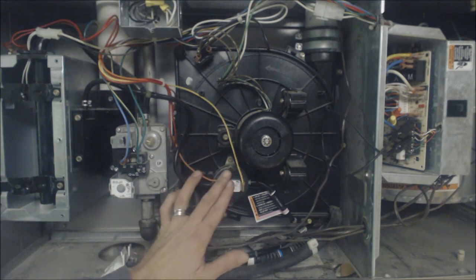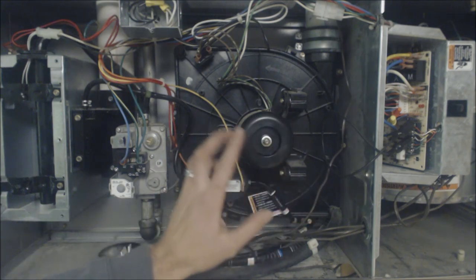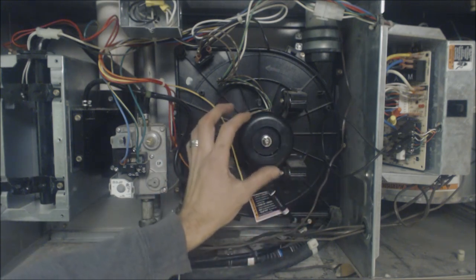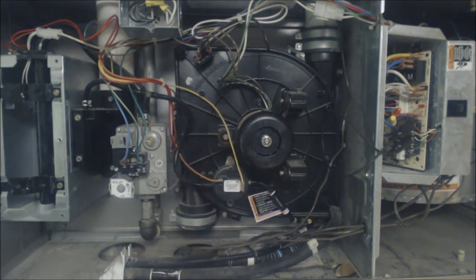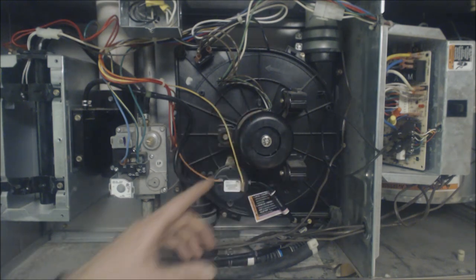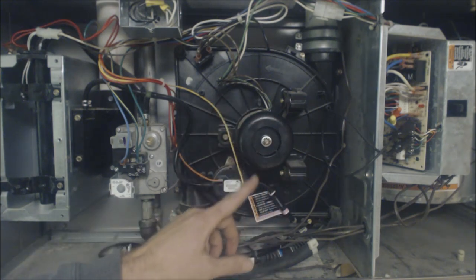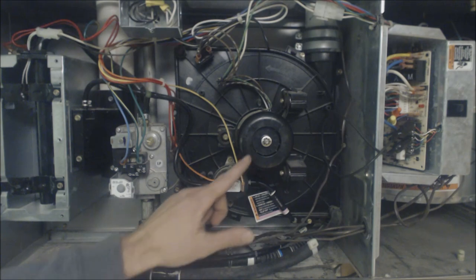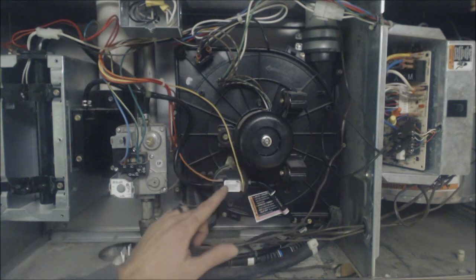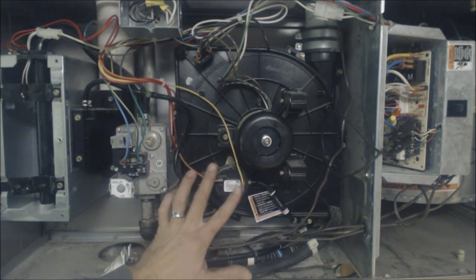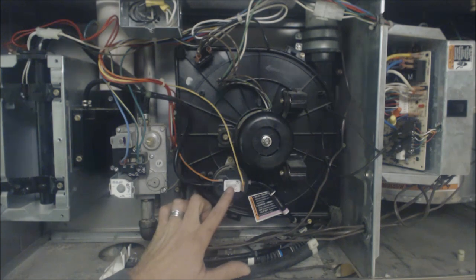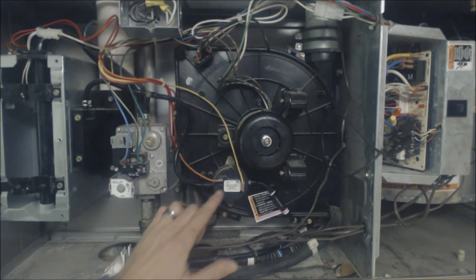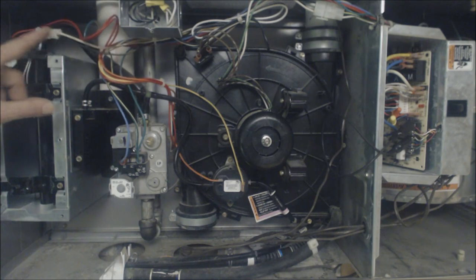But basically what it's doing is making sure that this is running, okay. But let me get back to the sequence of operation: the inducer motor runs, turns on 120 volts goes to it, then the pressure switch closes the 24 volt electrical signal, then the hot surface igniter right here turns cherry red, 120 volts applied to that.